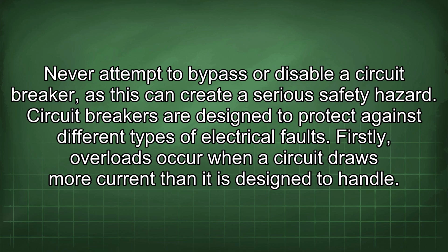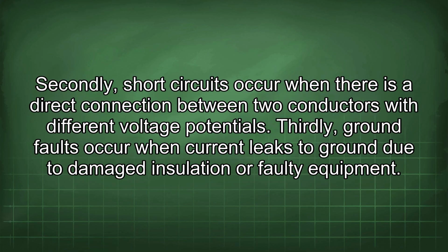Circuit breakers are designed to protect against different types of electrical faults. Firstly, overloads occur when a circuit draws more current than it is designed to handle. Secondly, short circuits occur when there is a direct connection between two conductors with different voltage potentials. Thirdly, ground faults occur when current leaks to ground due to damaged insulation or faulty equipment.